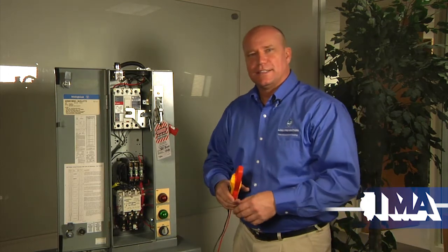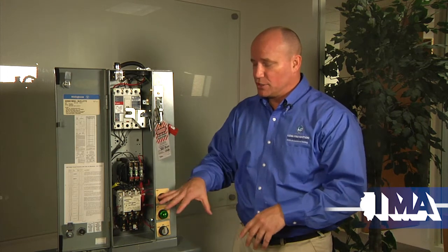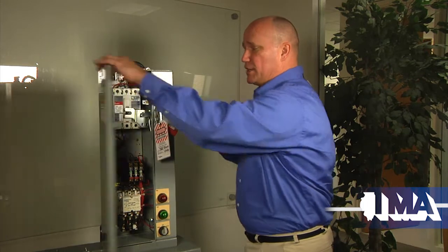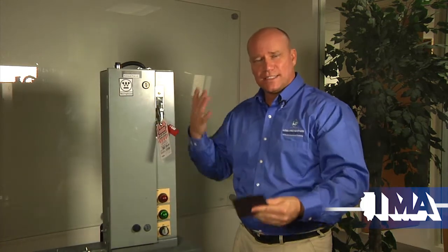Basically, that's it. It's a simple process which, if done correctly, is going to save you from being electrocuted or, worst case, shocked. Just make sure you can work it without the personal protective equipment. I hope everybody learned something today. I'm glad I had the opportunity that IMA gave me to get in front of you, because the process, in my opinion, is very important, and how you do it correctly. I encourage all facilities to get a copy of NFPA 70E. That way, if you don't have an arc flash analysis, or if you do and some of the equipment is not included in it, which is often the case, you at least know how to select the appropriate level of PPE based on the scope, the type of equipment, and the tasks you're actually performing.